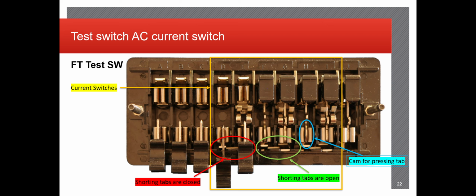As I said before, this is extremely important for current circuits because you never want to have an open CT circuit, or it could lead to disastrous consequences. But as shown in the middle F and G switches, when the test switch closes, it releases the shorting tab and opens the circuit up, allowing the current to not go directly to ground, and it'll just run up through the test switch up to wherever it's going.